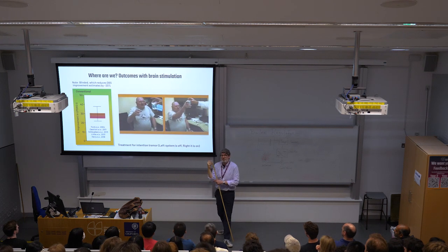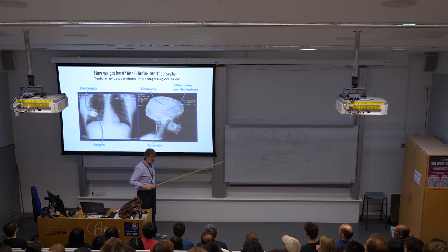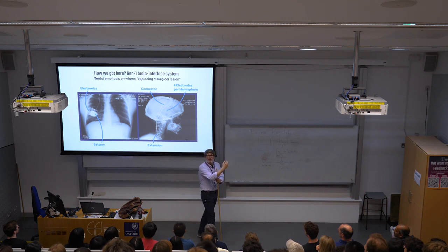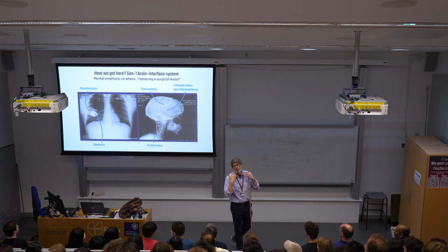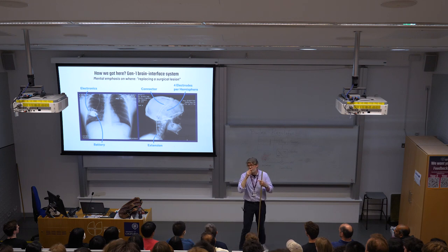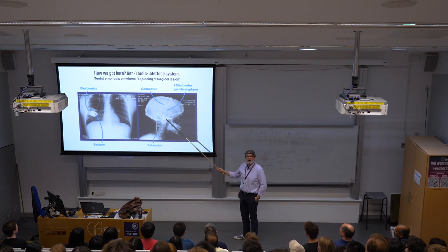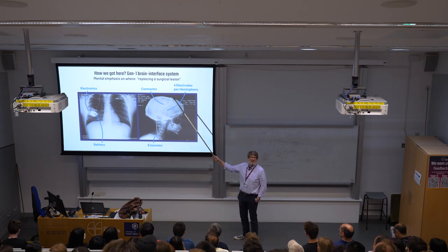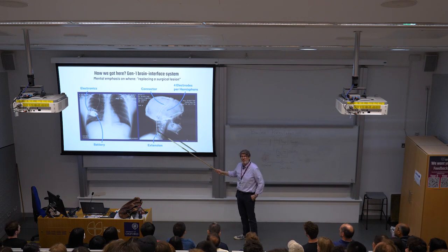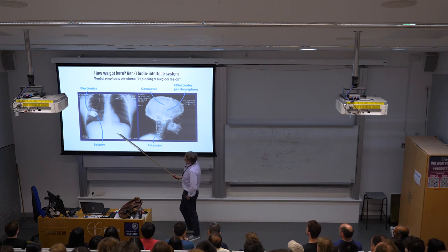It'll eventually, because of where they put this device in his brain, which is this next level, and the thalamus, if we turn up the amplitude, we'll actually start to get paresthesia, which is that funny pins and needles prick you get when you hit your funny bone. So we'll have that. It will also impact your speech, start to get a frog in his throat called dysarthria. And so we're challenged as engineers working with physicians to find this window, a therapeutic window, and make it as big as possible between when you start to get a good response to the disease symptoms, but the upper limit is when you start to actually get side effects that work against you. And so we're always thinking about ways to improve that therapeutic window to do a better job of treating these patients.